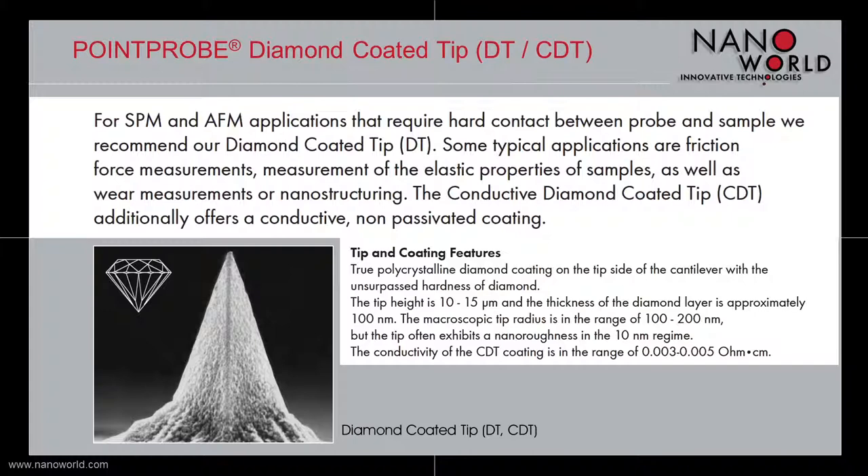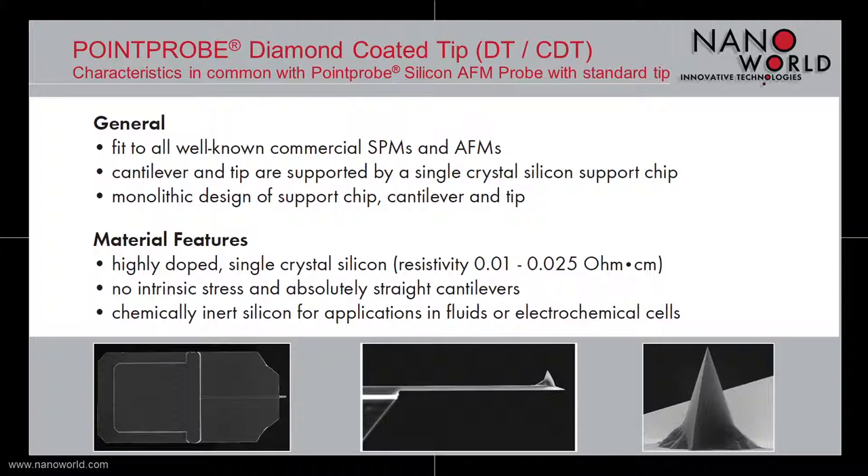The tip height is 10 to 15 µm and the macroscopic tip radius is between 100 and 200 nm. The true polycrystalline diamond coating, which is deposited on the tip side of the cantilever, gives the tip an unsurpassed hardness. The conductivity of the conductive diamond coated tip is in the range of 0.003 to 0.005 ohm centimeters.